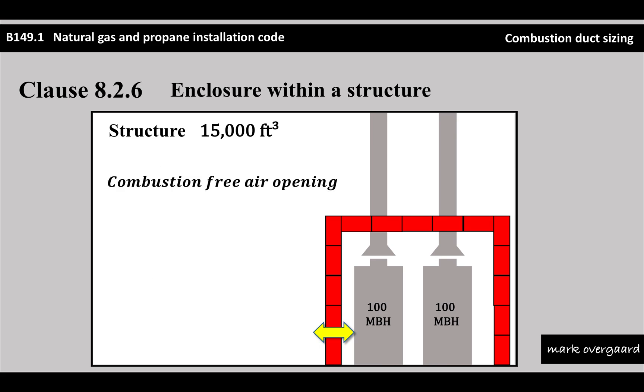If we do a calculation for our combustion free air opening, you would take the total input divided by 1,000 BTUs per inch squared - that's how much we need. So you'd go 200,000 divided by 1,000, and we'd end up with 200 square inches. That's going to be the size of that opening down there. So far, so good.